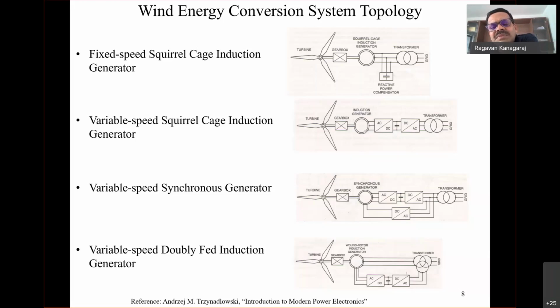So whatever may be the speed, even if it is very less - let's say we have designed for 1500 rpm as synchronous speed, and now the speed is just 500 rpm - that's fine, you can still connect. The reason is the frequency of the output from the machine may now be 10 hertz, 20 hertz, because it's connected with the wind speed. With whatever gearbox we have, we may be getting very low speed, only 20 hertz. That doesn't matter - that 20 hertz can still be connected to the 50 hertz grid with the help of this frequency converter, right?